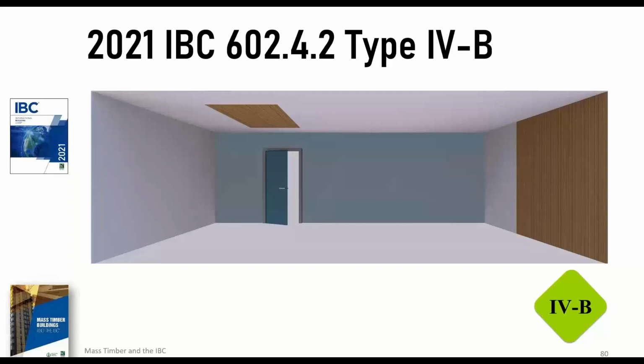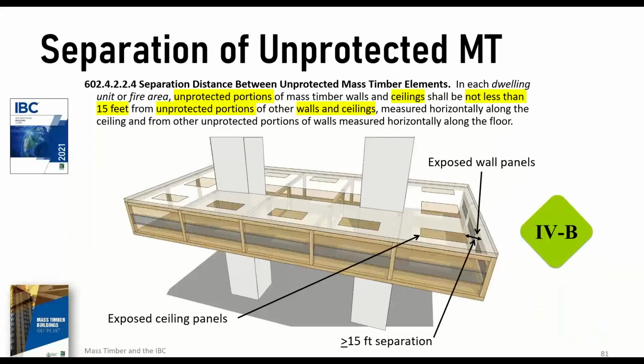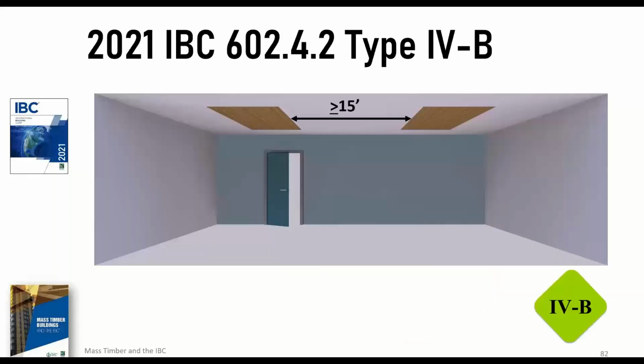So here's a potential configuration. We have an exposed wall assembly on the far right, and we have an exposed ceiling assembly above the door. And we'll get into a little bit more detail with these, but they're typically mandated at 15 feet apart. So you can have exposed ceilings and walls, but they have to remain over 15 feet apart. So there's the code language there, separation of unprotected mass timber, 602.4.2.2.4. Dwelling unit or fire area, unprotected portions of mass timber walls and ceilings shall not be less than 15 feet from unprotected portions of other walls and ceilings measured horizontally from the ceiling and from unprotected portions of walls measured along the floor. And it's just hammering home that there has to be a 15-foot separation between the unprotected surfaces in type 4B construction.